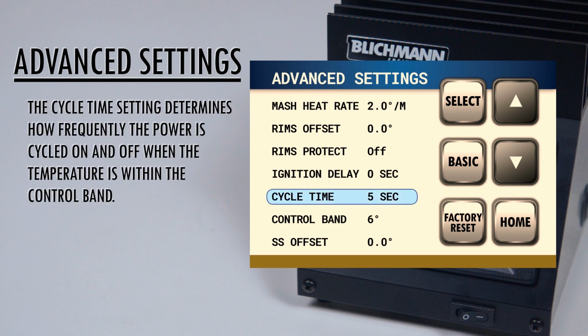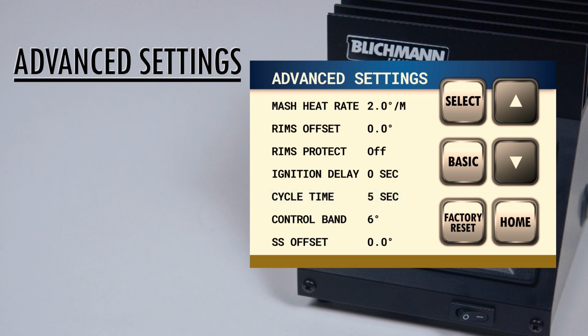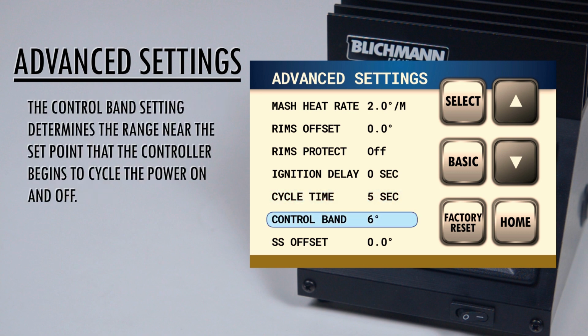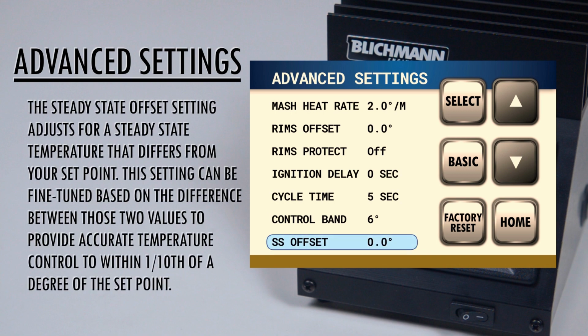The cycle time setting determines how frequently the power is cycled on and off when the temperature is within the control band. The control band setting determines the range near the set point that the controller begins to cycle the power on and off. The steady state offset setting adjusts for a steady state temperature that differs from your set point. This setting can be fine-tuned based on the difference between the two values to provide accurate temperature control to within 1/10 of a degree of the set point.